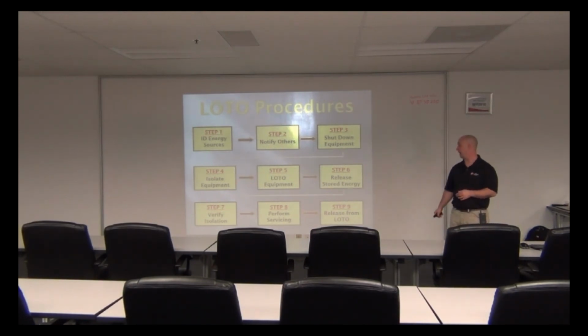Isolate the equipment by basically powering off what is supplying energy to it, and then you're going to lock out that piece of equipment. You'll release the stored energy - that's going to be a capacitor, any extra air in a line, any hydraulics left in a line. You're going to bleed all that out and make sure there's nothing in it, so it can't be released whenever you open up whatever it is.